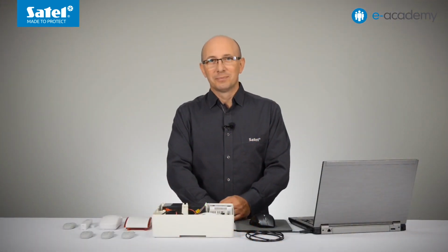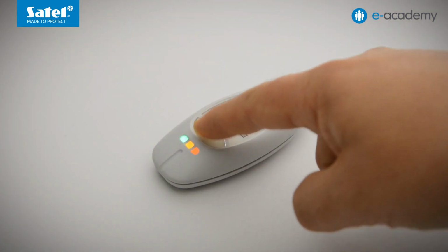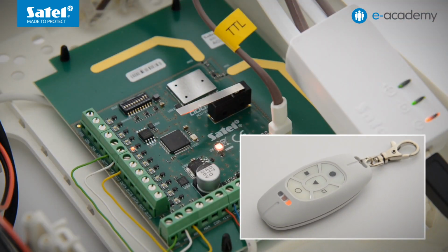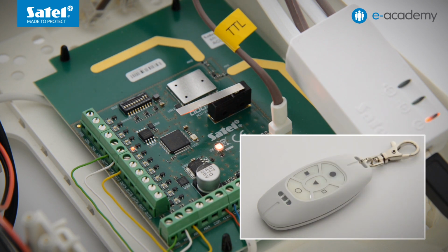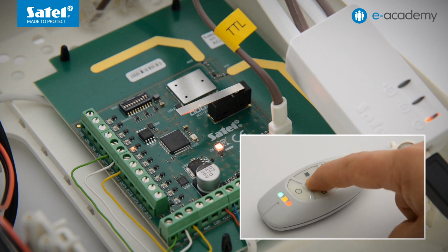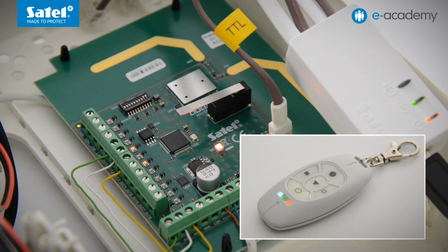Let's check how it works. I press the empty circle button. The out1 output has been activated. A red LED has signaled the violation of the AR1 input. Now I will use the empty square button. The out2 output has been shortened to ground for 5 seconds, hence the AR2 input will also be violated for such time. The red and orange LEDs have confirmed violation of the AR1 and AR2 inputs. I press the triangle button. The out3 output has been activated for 10 seconds. The red and green LEDs have come on to confirm the violation of the AR1 and AR3 inputs.